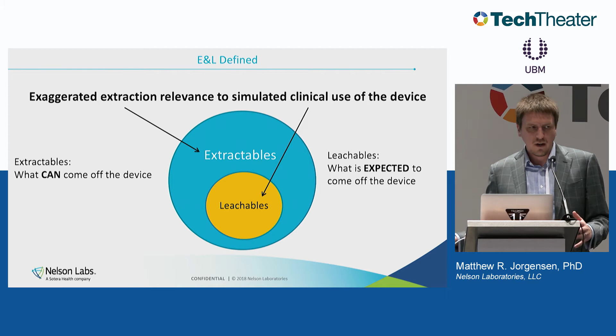Extractables are chemicals that can come off of a device or leave device materials when exaggerated, aggressive conditions are used, things that we know are going to be worst case compared to clinical use. And then leachables are what we expect during actual clinical use in contact with the body. So for extractables, we use something like hexane, which is a pretty aggressive solvent, at 50 degrees C, an elevated temperature, for 3 days. And whatever comes out under those conditions, we'll say, okay, this is the amount that could come off every day for the rest of the patient's life. So it's a really exaggerated scenario. If we went to leachables, we do something like saline at 37 degrees C for 24 hours. So that's really the key difference.